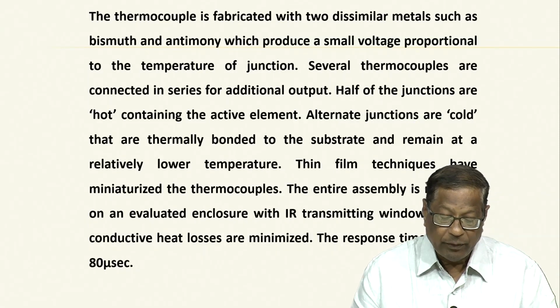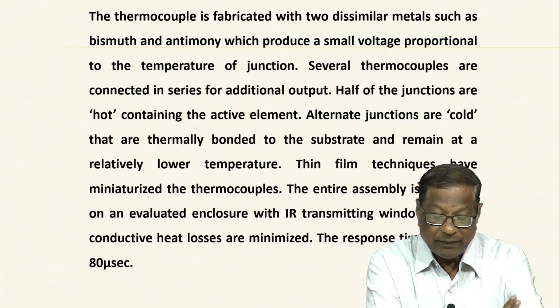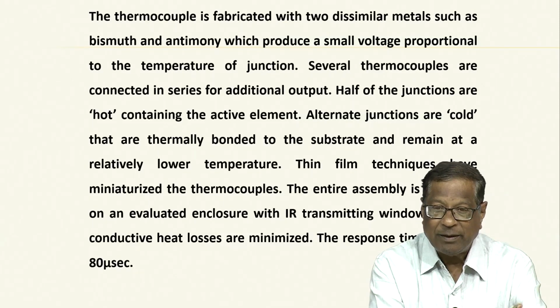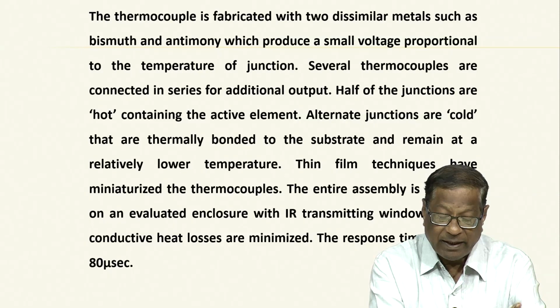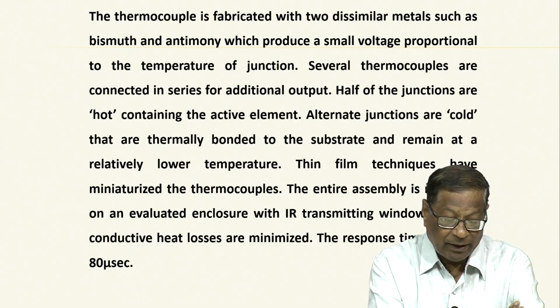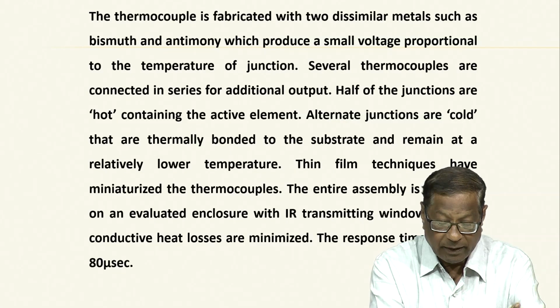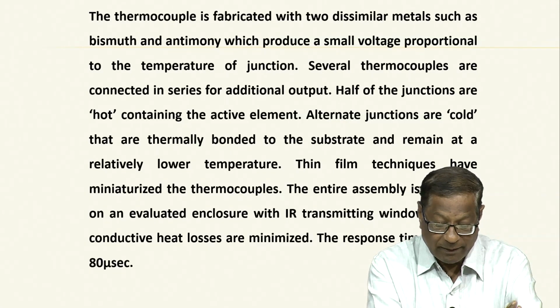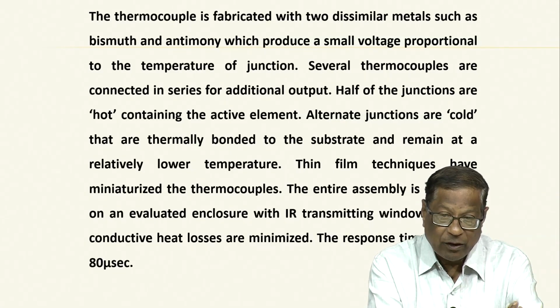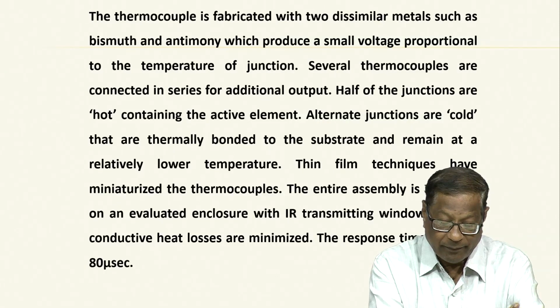Thin film techniques have miniaturized the thermocouples. The entire assembly is mounted in an evacuated enclosure with an IR transmitting window, so that the conductive heat losses are minimized.